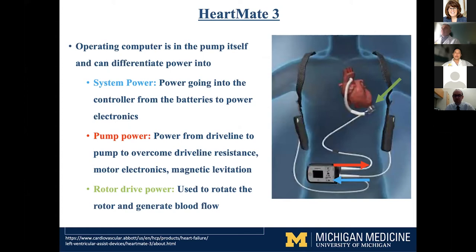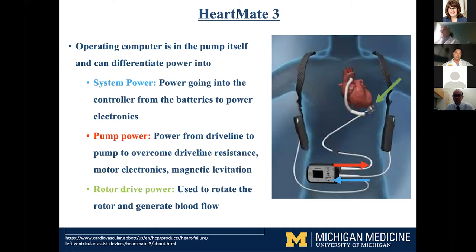A lot of the computing power is in the pump itself, which allows it to differentiate how much power it's delivering to each component. There's system power going to the controller from the batteries to power electronics in the controller, then pump power which drives the driveline and overcomes driveline resistance, and also power to keep the rotor elevated and to power the motor electronics. The important component is the rotor drive power, which is used to actually rotate the rotor and generate blood flow. Being able to pinpoint exactly how much power that's using is very powerful and allows us to determine flow.